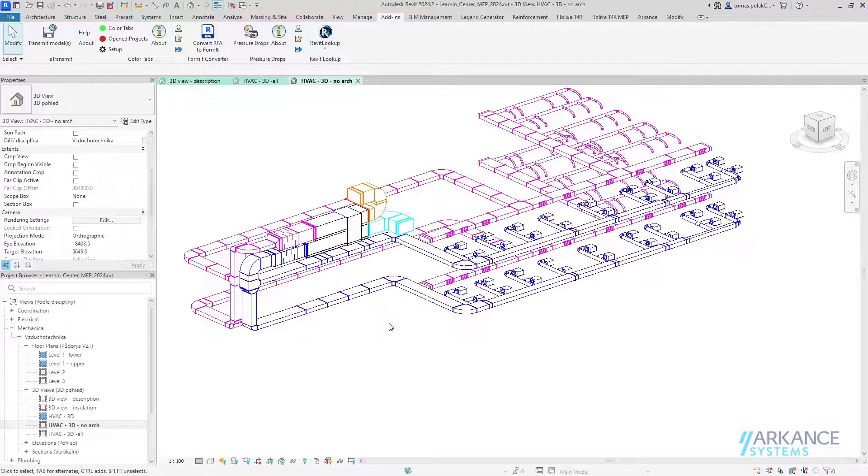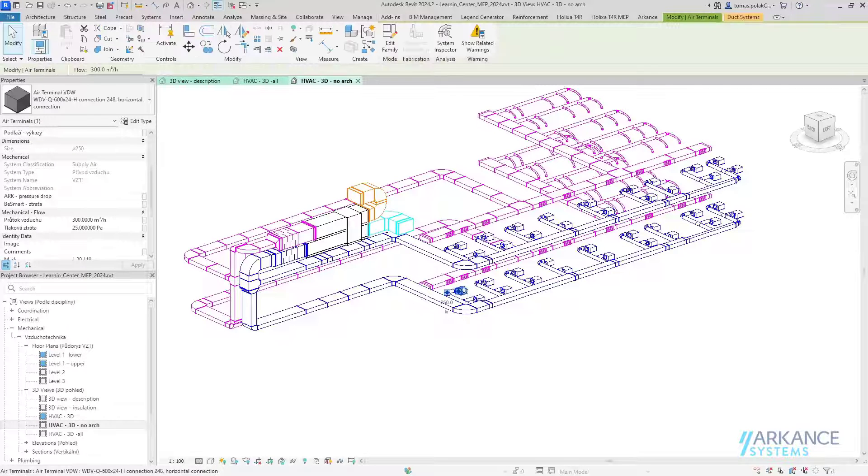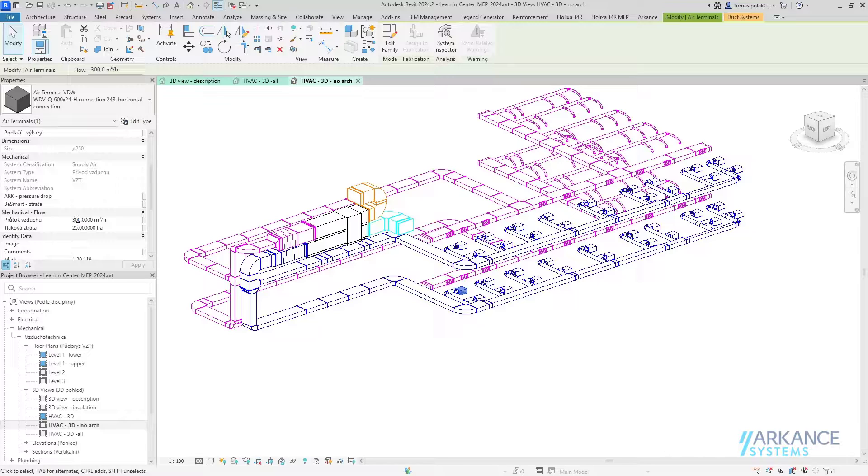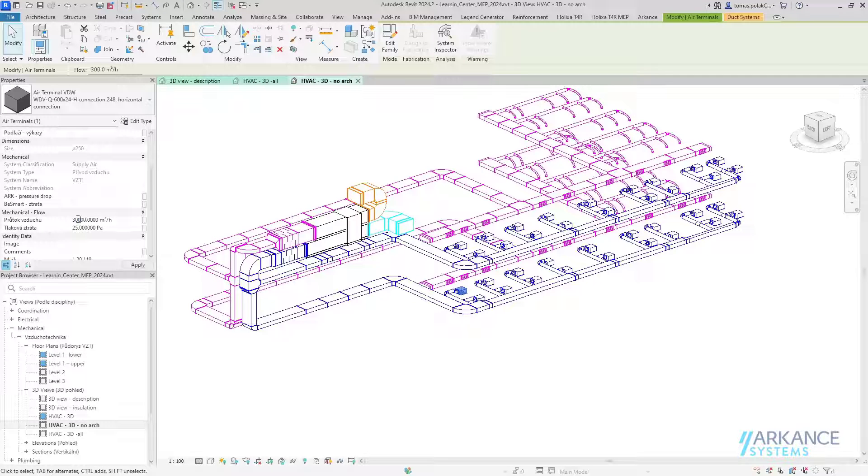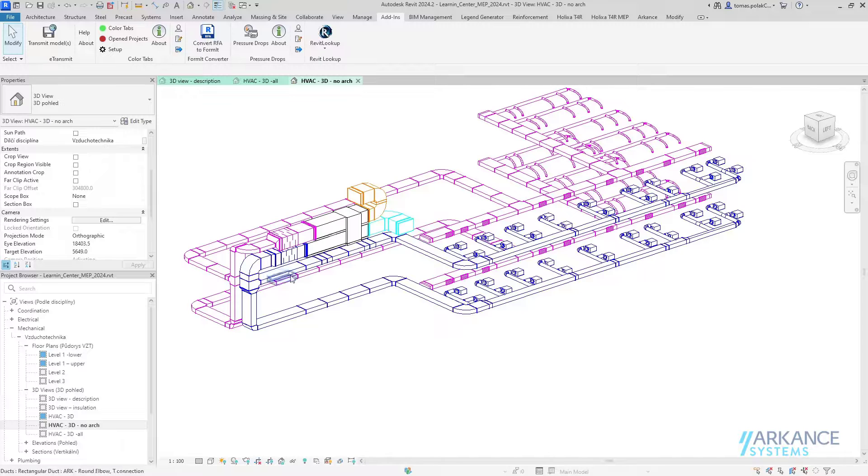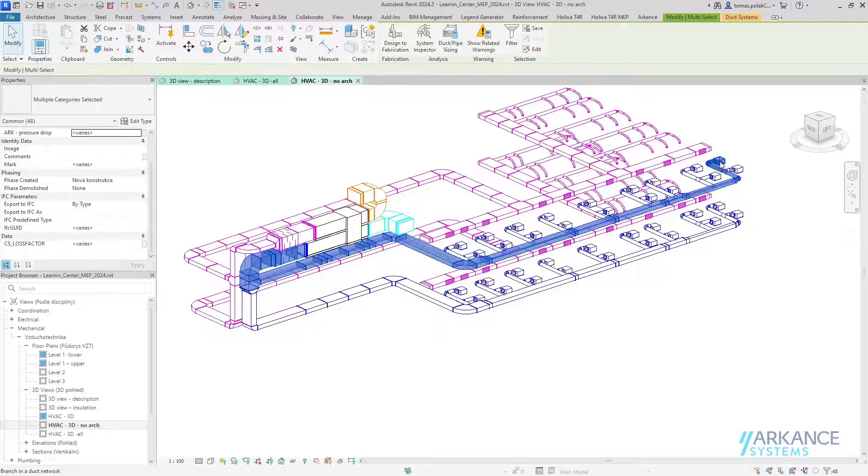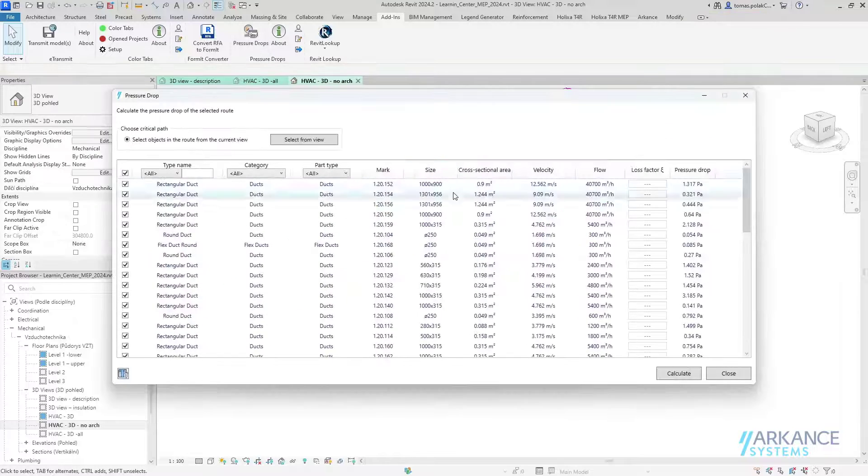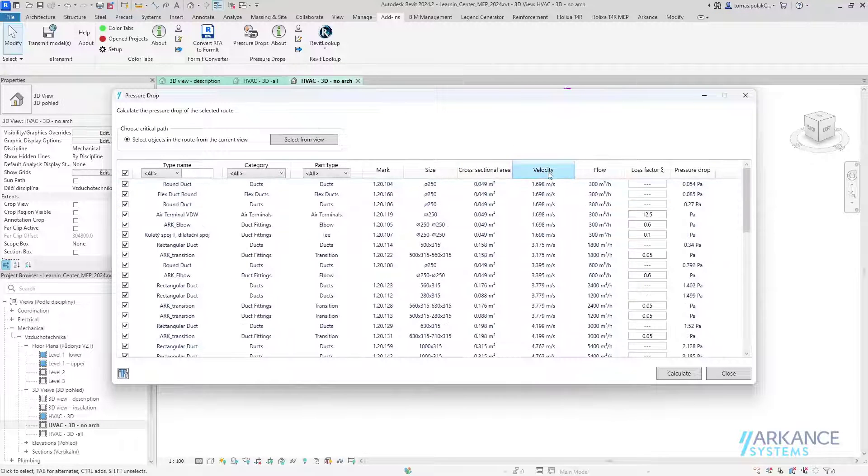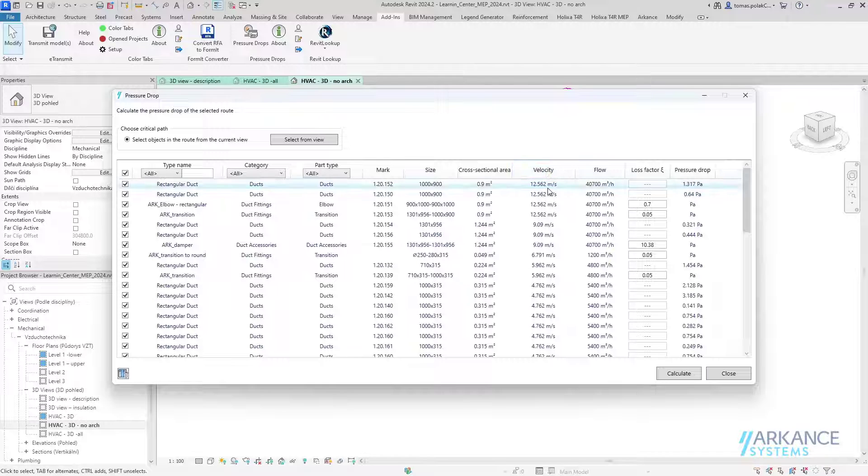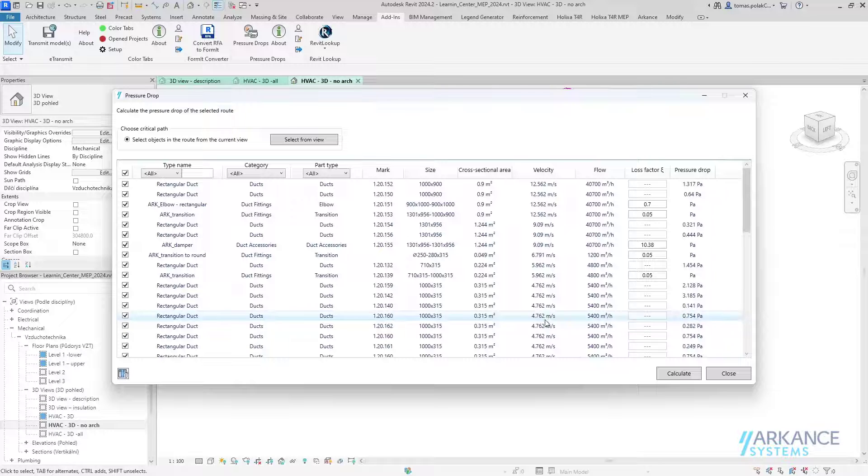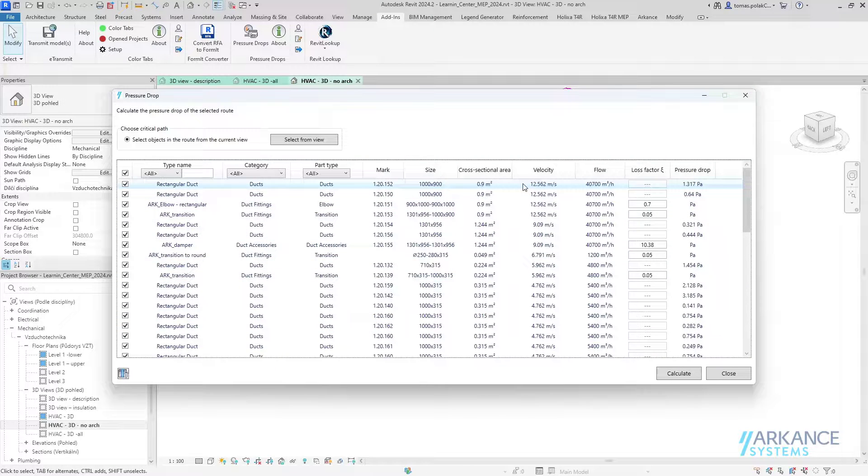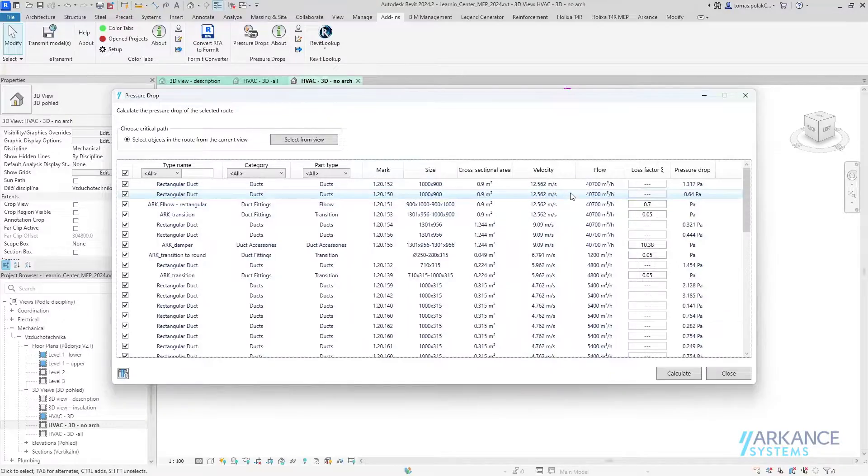Now let's take a look at some other advantages that Pressure Drops offers. First, it's a quick analysis. If I change the flow of this system to some out-of-this-world value and now calculate the path that I did previously, if I check the velocity, you can see that in this part the velocity is too high and it's not conforming to the local code, which I can see clearly here.